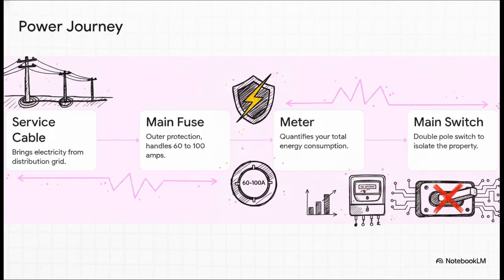So a service cable, either running overhead or buried underground, taps into the local distribution grid and comes straight to your property. First stop? It passes through the service head, which holds your main fuse. This fuse usually handles between 60 and 100 amps, and it basically acts as the outermost wall of your electrical fortress, making absolutely sure a massive surge doesn't just overwhelm your house. After that, it flows into the electricity meter, which just tallies up your energy consumption.